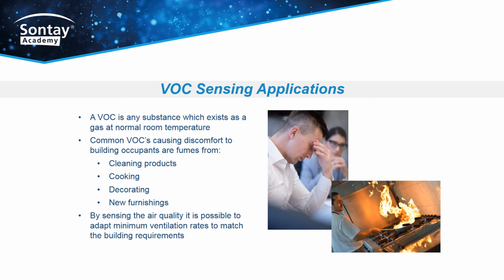VOC sensing applications. A VOC is any substance which exists as a gas at a normal room temperature. Common VOCs causing discomfort to building occupants are fumes from cleaning products, cooking, decorating, and new furnishings. By sensing the air quality, it is possible to adapt minimum ventilation rates to match the building requirements.